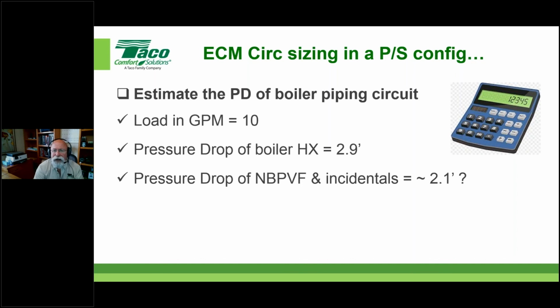As long as that boiler manufacturer did not add for the incidental pipe, valves and fittings, then you're going to have to add for that slightly. But when it's appropriately sized, and relatively short, like most of the near boiler piping is on the primary side of a primary-secondary configuration, then it's usually a foot or 2 feet of head, maximum. So again, we take things into consideration like, is there a magnetic dirt separator on there? Are there balancing valves that somebody has cut in there? That sort of thing. That all has to be considered in that estimate.